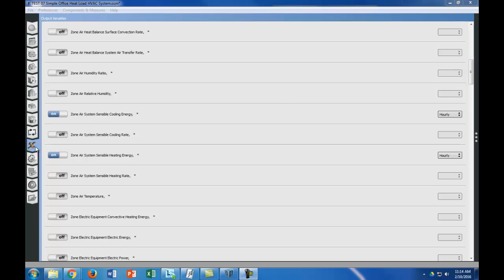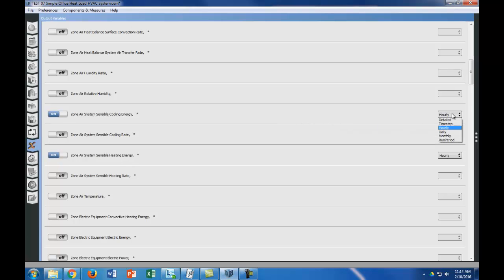Turn on any output variables you want. If you're looking to do heating and cooling load for zones, you want to turn on the zone air system sensible cooling energy and the zone air system sensible heating energy. You can choose whether it's detailed time step, hourly, daily, monthly, or annual run period. We're going to do hourly in this case.